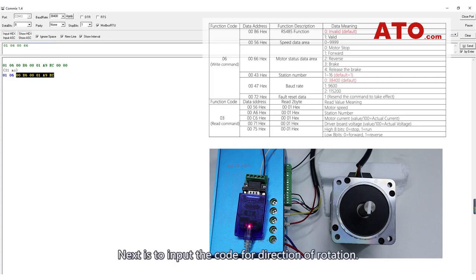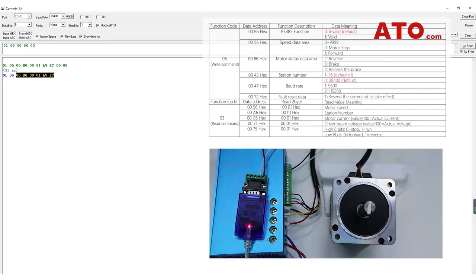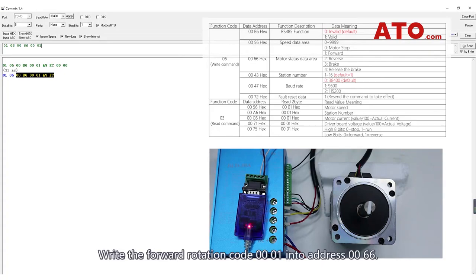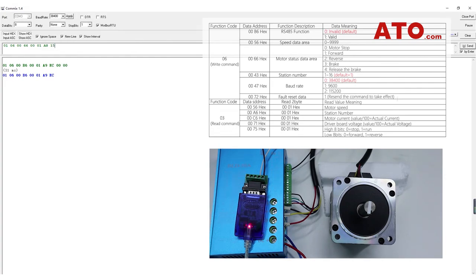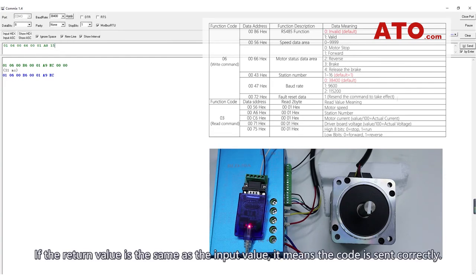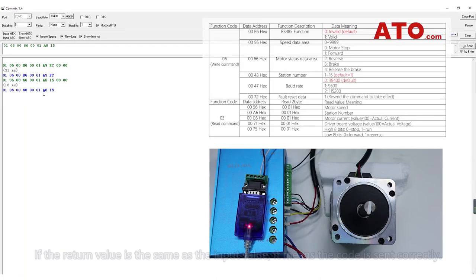Next is to input the code for direction of rotation. Write the forward rotation code 00001 into address 0066. If the return value is the same as the input value, it means the code is sent correctly.